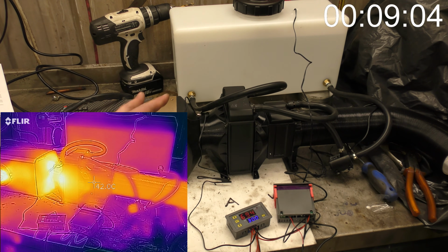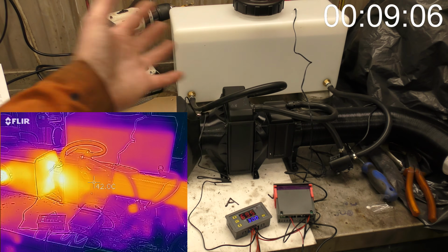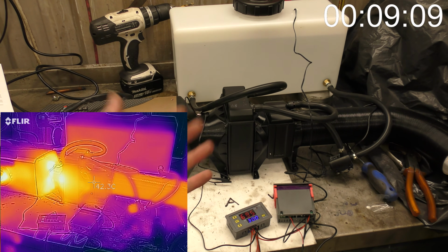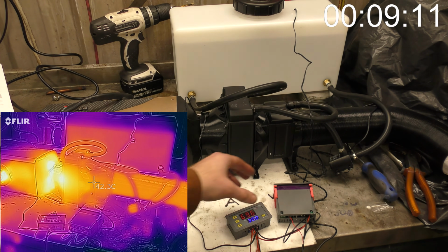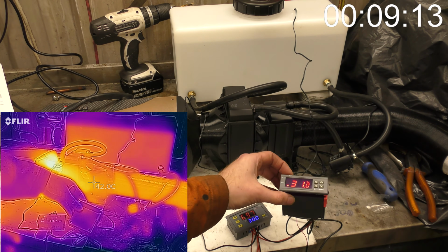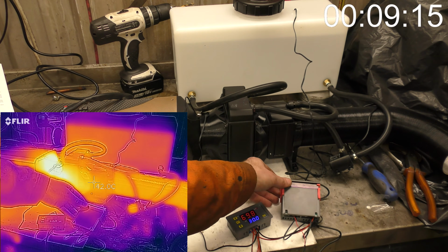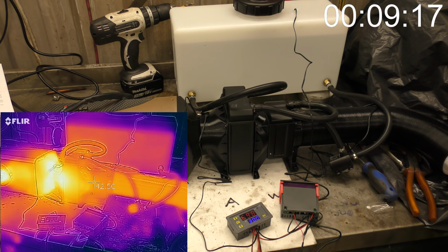But if you're going to heat it up and add an insulated tank to keep it, you would need to heat it to like 65, 70, 78 degrees to actually kill all the bacteria, because you don't want warm stagnant water - that gets you Legionella. You do not want that.